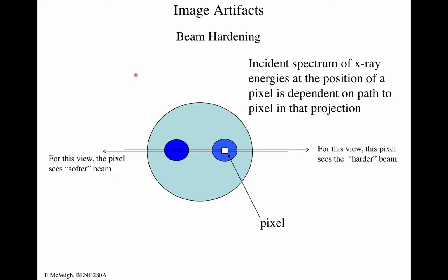And the reason was we filtered those out with a piece of copper or aluminum such that those low energy photons didn't hit the patient. Right? And some of the filtering is naturally done by the target itself and some by the glass, etc. But then we put a copper filter in front of it. So in a way, what we've done there is we have taken the average energy of the X-rays that were created at the target, and we've increased the average energy of the beam coming out by getting rid of the low energy photons. Right? The patient also does that.